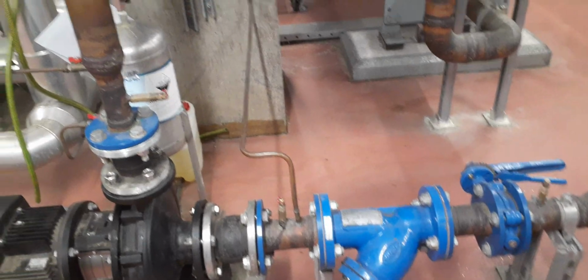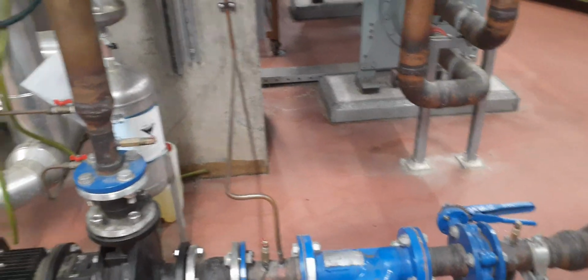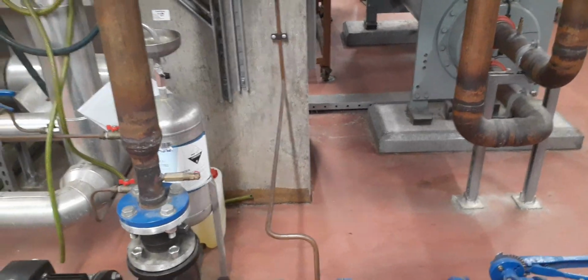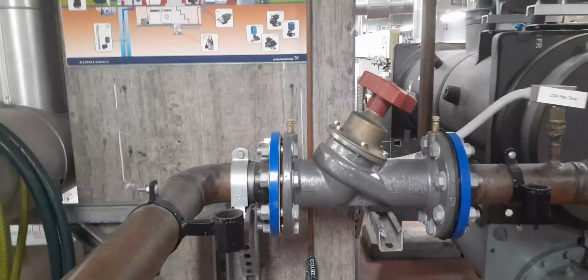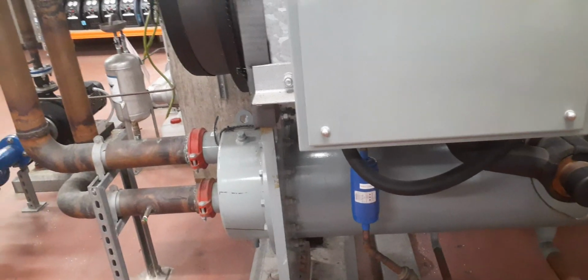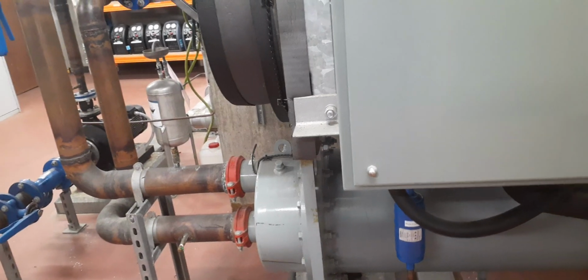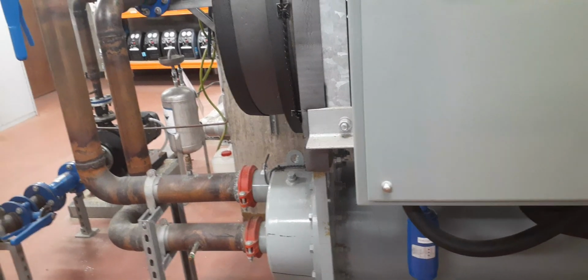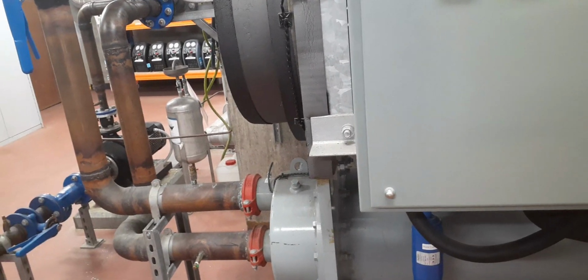Now, perhaps don't worry about this one here because this is actually going via a heat exchanger. Now, that's a balance valve. That's not a major component. All right, so we have the water coming in at 29 and leaving at 35. That's a standard. That condenses refrigerant. If it's working on standard pressures, the shell and tube condenser would be condensing at, for water cooled, what would that be? You can say it. Yeah, you've just indicated with your hands, 40, that's right, okay.